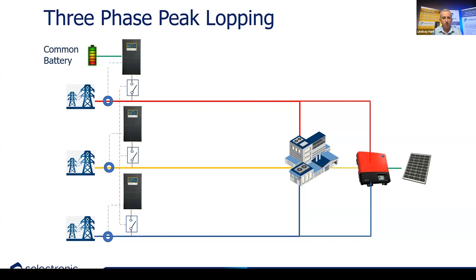And this is where we can add some SP Pro bidirectional inverters. Did I say Australian made? Made in Melbourne before? I might have said that, I think. And basically, we're going to add some storage onto the three phases of the system. So effectively, let's just say for a simple design rule, we don't want to take any more than 100 kilowatts, or we can't take any more than 100 kilowatts from that grid supply. Let's say we want 120 kilowatts. Then what we're going to do is we're going to add a 20 kilowatt bidirectional inverter, the SP Pro, onto each phase to increase our capacity.